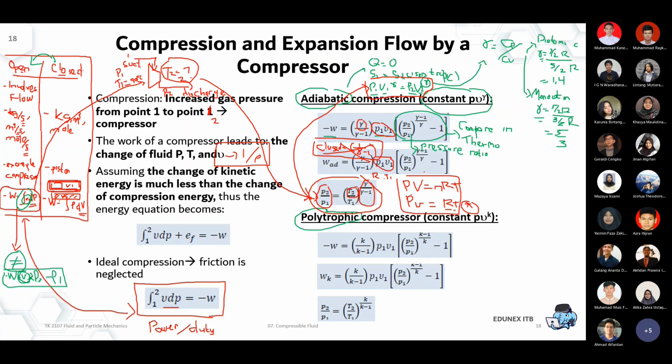So you can calculate. If you remember my previous lecture about the compressor, I stated that the typical compression ratio is about 3 for a centrifugal compressor. I mentioned it before. The typical one would be limited at around 3. Let's say we use that rule of thumb, and we try to compress a gas from ambient temperature. Let's say ambient is 30 degrees C, that's 303 Kelvin.